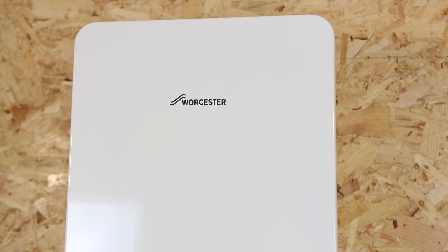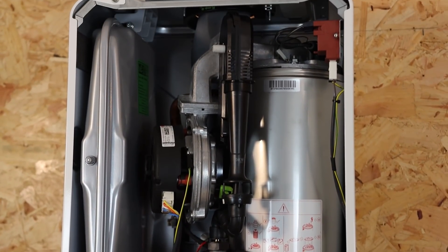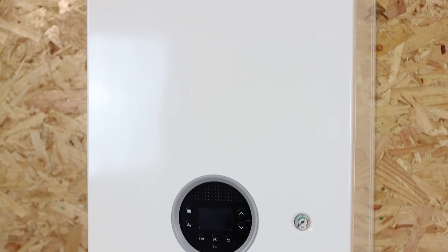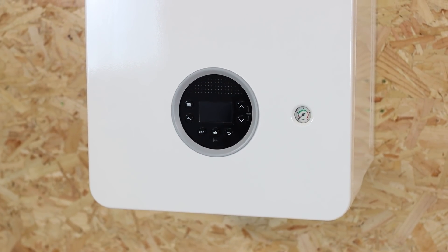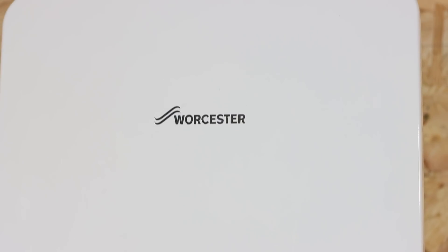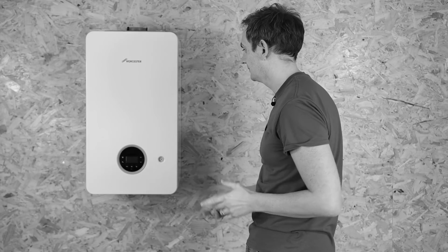To calculate the kilowatts needed, stick to this formula: 1 kilowatt for small radiators or towel radiators, 1.5 kilowatts for an average size radiator, and 2 kilowatts for a really big double radiator. Add them all up together and that gives you the total kilowatts needed. It'll only take five minutes and it's better than watching Cash in the Attic.